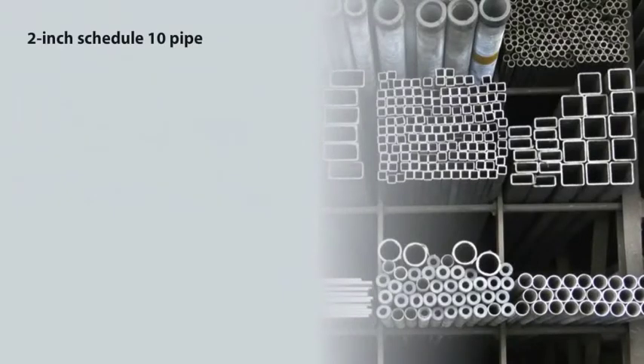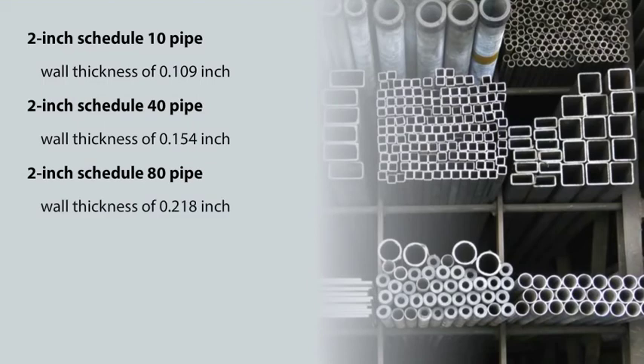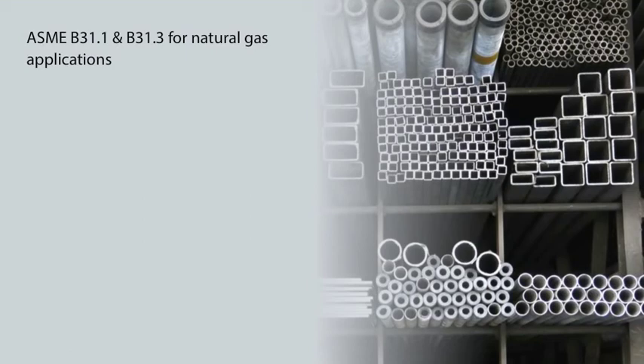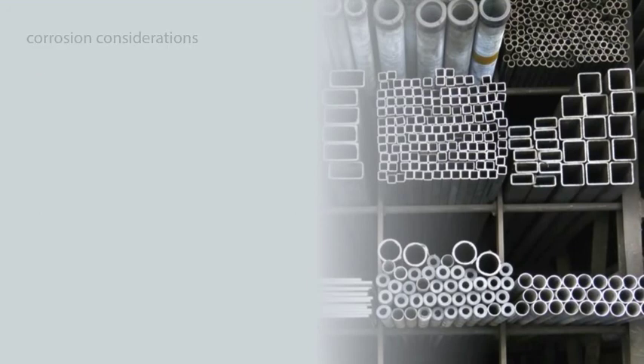The higher the schedule number, the thicker the pipe wall and the smaller the inside diameter. For example, a 2-inch schedule 10 pipe has an approximate wall thickness of 0.109 inch, a 2-inch schedule 40 pipe a wall thickness of 0.154 inch, and a 2-inch schedule 80 pipe a wall thickness of 0.218 inch. Guidance on pipe thickness calculations can be found in ASME B31.1 and B31.3. You may want to specify schedule 80 for fuel gas piping systems in areas where corrosion is possible, even if not needed from a pressure rating perspective, as adding material for corrosion considerations is a traditional practice in process plant design.